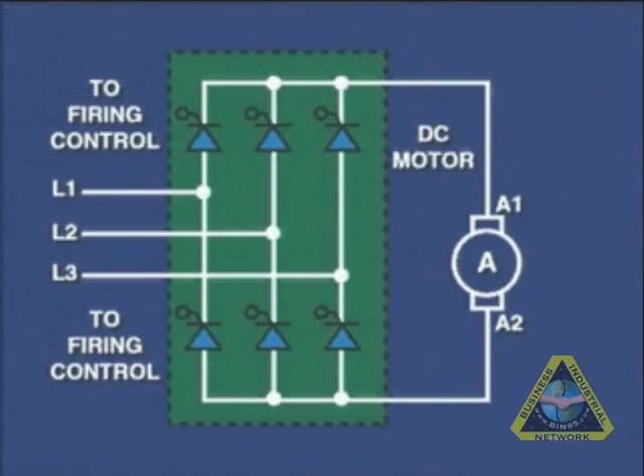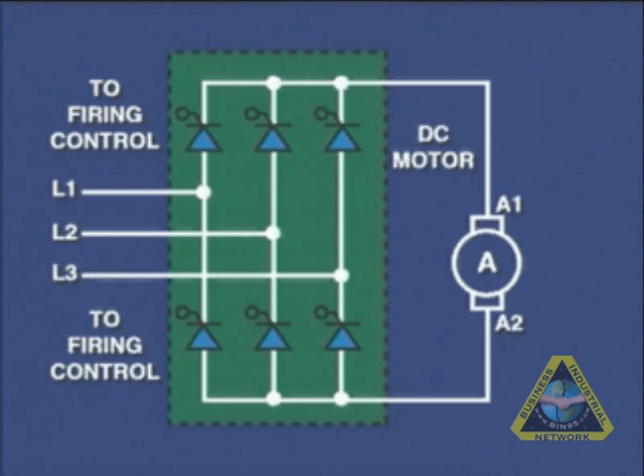If a problem is suspected with the drive, in this case one which uses a so-called six-pulse bridge, the first thing to do is to check for proper operation of the SCRs, making sure they are firing and providing power to the motor.